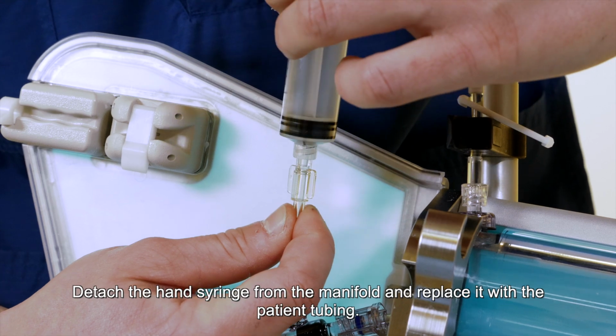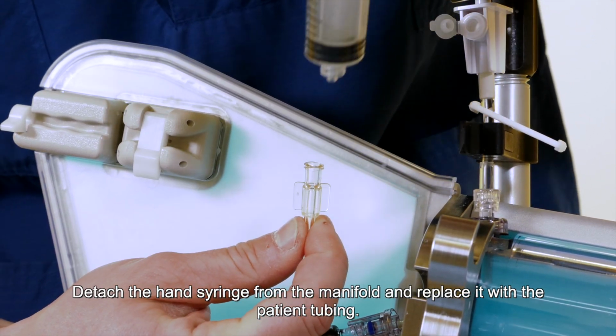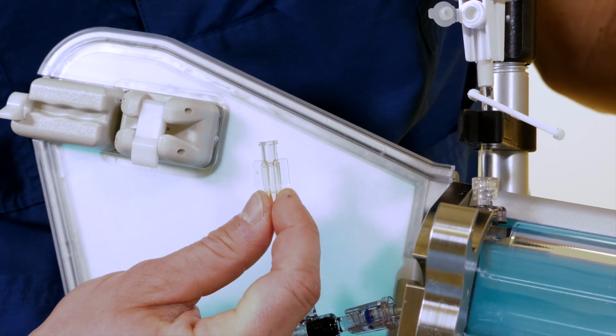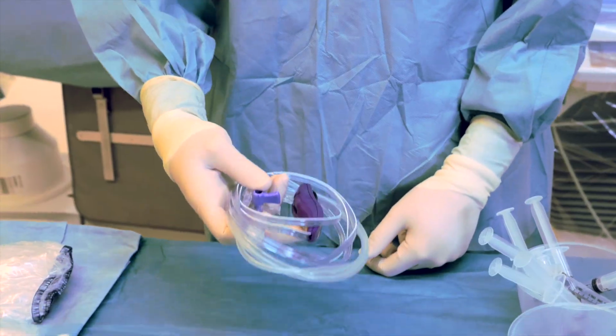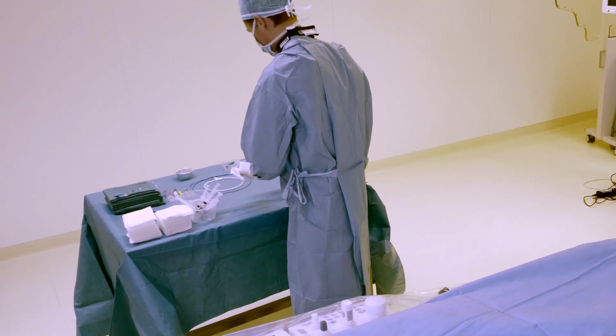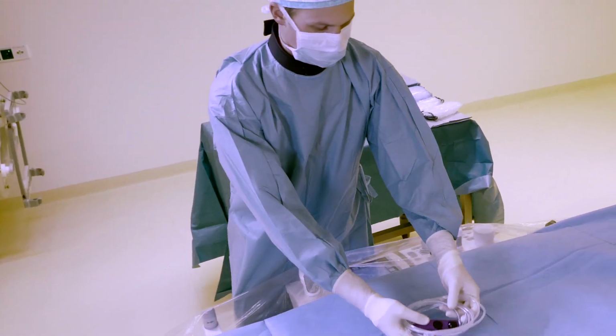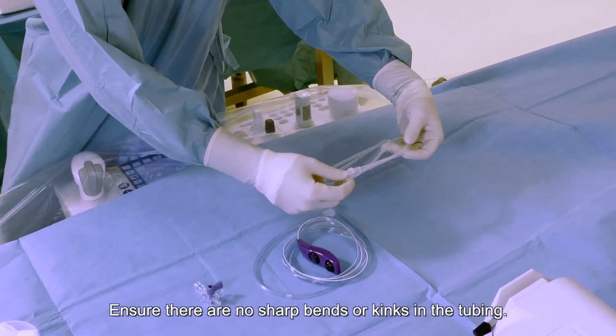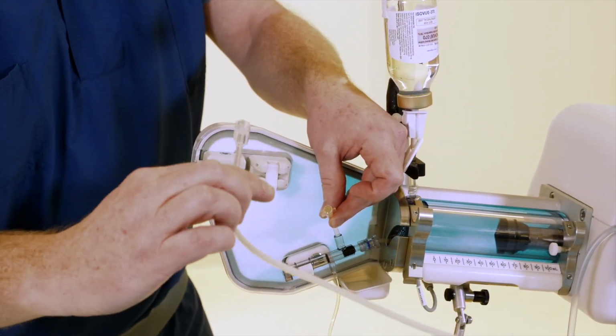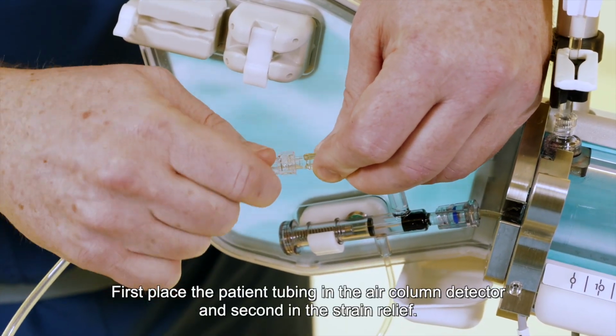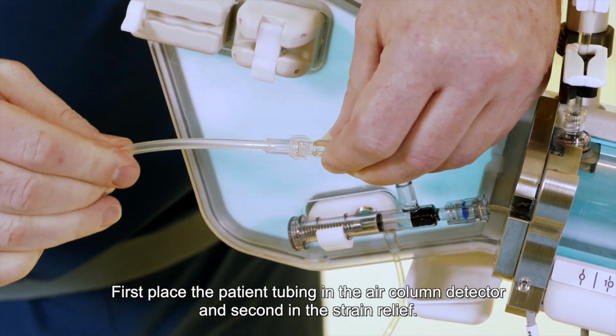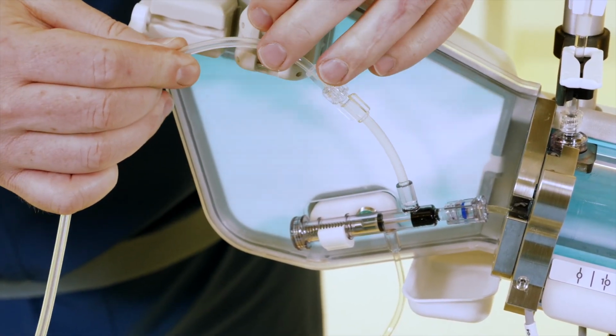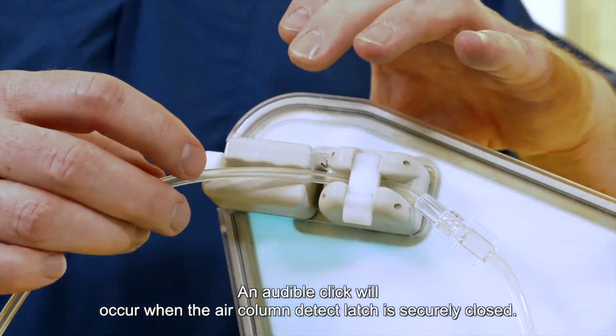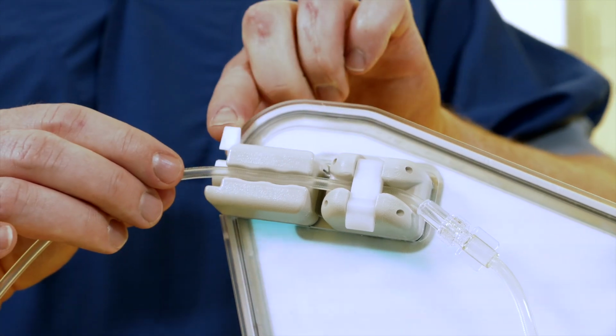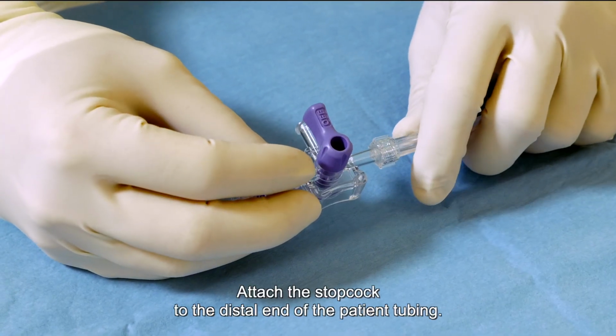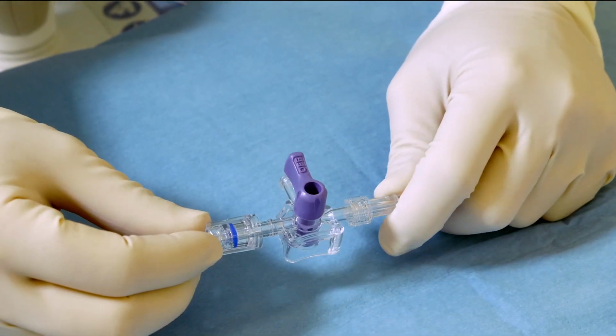Step 1. Detach the hand syringe from the manifold and replace it with the patient tubing. Ensure there are no sharp bends or kinks in the tubing. Step 2. First place the patient tubing in the air column detector and second in the strain relief. Fully close both latches. An audible click will occur when the air column detect latch is securely closed. Step 3. Attach the stopcock to the distal end of the patient tubing.